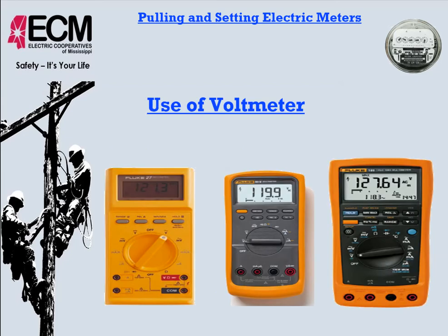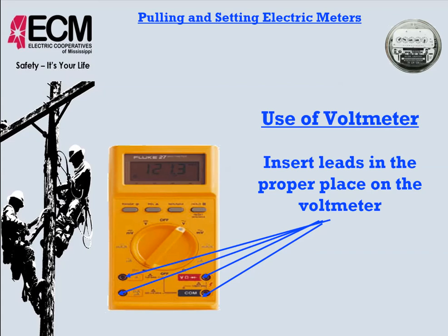Use of voltmeter. You should be familiar with the device that you're operating. If you're not, you should read the operator's manual to learn how that piece of equipment or device should be used properly, making sure that you are set to the proper setting on your multimeter, and also making sure that the leads are plugged into the right place depending upon what you are measuring. Now, not all voltmeters require this. Some are multimeters, they digitally range and swap to the different things, but this one has, depending on what you're testing. Here you would test for volts and resistance on the same lead, but over here would probably be for current or something like that. It would need to be plugged in somewhere differently.